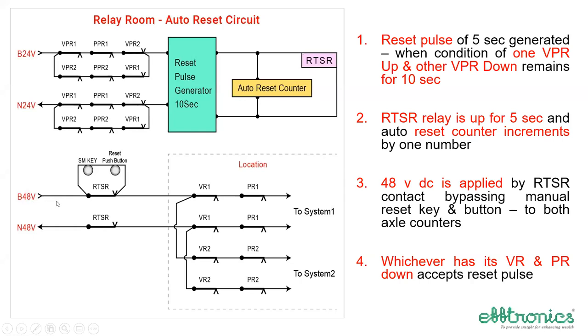But the only thing is, it has to reach system one and system two only when conditions are suitable. What are those conditions? Number one, one of the axle counters must have failed, and that causes the RTSR relay to pick up for a time of 5 seconds only. Just for 5 seconds, it picks up. During that 5 seconds, 48 volt DC travels from the station to the location, and at the location, again, there are two paths to system one and system two.